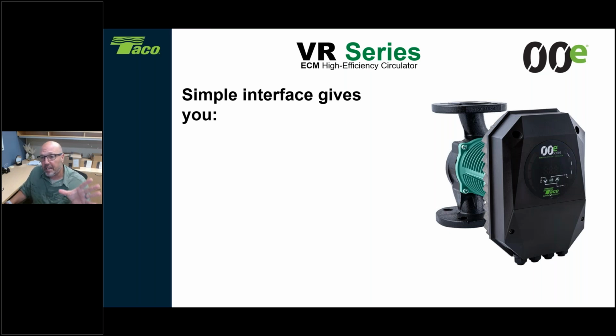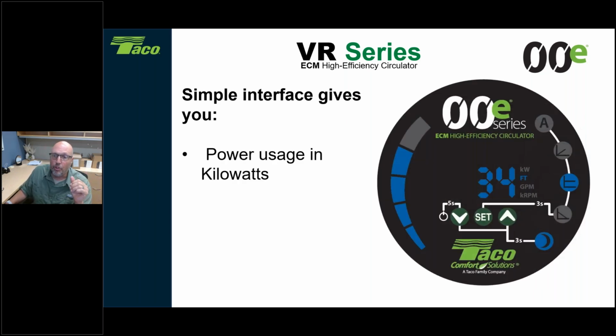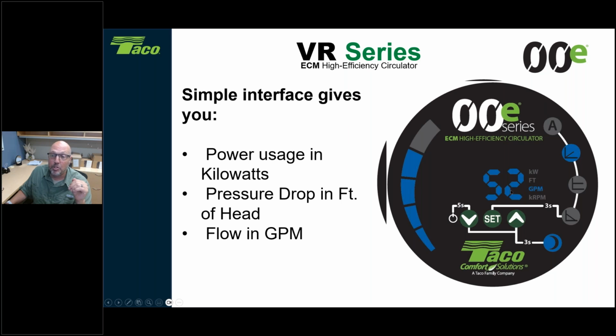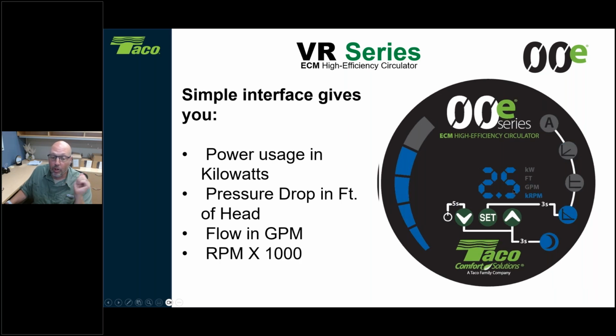The faceplate gets us a lot of programming. You can see when this is up and running, it is going to give you the power consumption right at that moment in kilowatts. It gives you the pressure drop in feet of head. All right, and this will rotate every couple of seconds as it's running. It gives you the flow in gallons per minute. Okay, and it will also give you the RPMs, the speed the circulator is running at that time period. And along the right-hand side, it's giving you the designation of what mode the circulator is operating in, and these are the modes that we talked about last week.